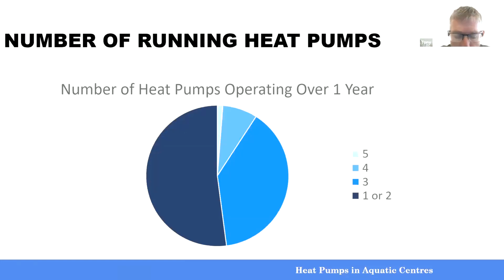So in this particular example, I did some work for an aquatic centre in Melbourne, and they had 5 heat pumps. Well, the design had 5 heat pumps. So from this, you can see that for at least half of the year, only 1 or 2 of those heat pumps will be running, and the other 3 will just be sitting there on standby. And then for 90% of the year, they'll be using 3 or fewer heat pumps. And only during the coldest months of the year will they need the last 2 heat pumps, with the final 5th heat pump only being needed when the temperature got below 5 degrees.